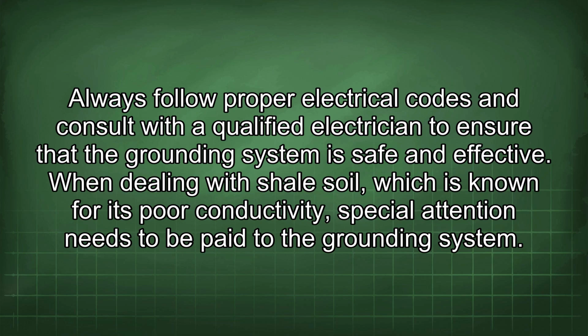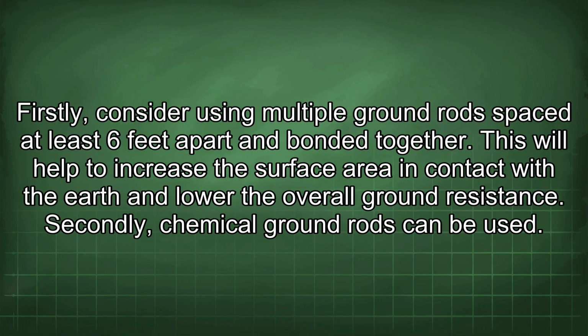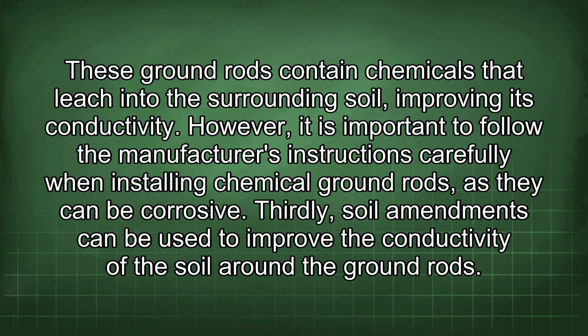When dealing with shale soil, which is known for its poor conductivity, special attention needs to be paid to the grounding system. Firstly, consider using multiple ground rods spaced at least 6 feet apart and bonded together. This will help to increase the surface area in contact with the earth and lower the overall ground resistance. Secondly, chemical ground rods can be used. These ground rods contain chemicals that leach into the surrounding soil, improving its conductivity. However, it is important to follow the manufacturer's instructions carefully when installing chemical ground rods, as they can be corrosive. Thirdly, soil amendments can be used to improve the conductivity of the soil around the ground rods.